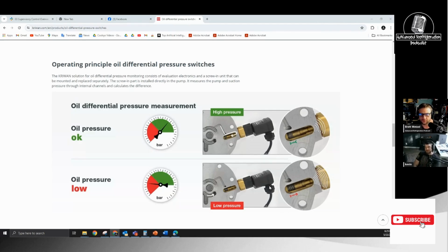See, that's what makes me angry. It's weird because sometimes you'll have schematics that do that, because typically all schematics are supposed to be shown with no power and no pressure applied. Correct. But I don't know how many times I've seen on prints a low pressure switch normally closed, which really doesn't make any sense, because theoretically, if the rack runs out of gas, that switch would be normally open. Correct. And so same thing with this.